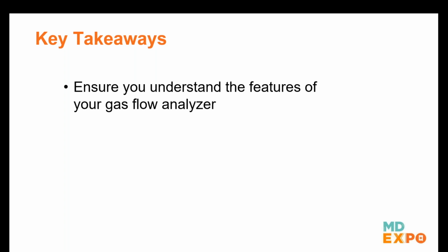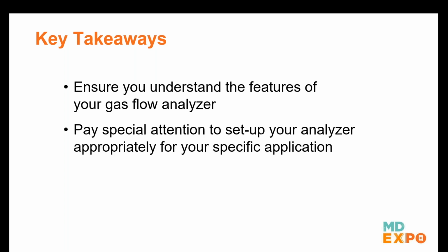Analyzers are like a multi-tool, right? Like the old Leathermans or Gerbers, or, you know, the original multi-tool, the Swiss Army knife. Lots of cool tools in there, but you need to know what they're used for, okay? Pay special attention to your setup, as we said before. Make sure you're setting up properly, making sure that all the settings are correct, that we keep harping on, gas standard, gas type. Something to do before you start measuring is warm up your device when you're setting it up. Okay, let it warm up, zero it out, get it ready to go, and then make sure your gas standards and gas types are correct, and then start your testing. Okay, make sure it's set for the specifics that you're trying to measure.